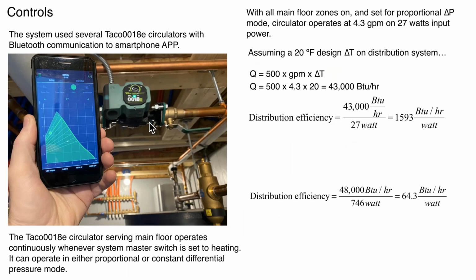There's that little pump that's running that, and there's an example on the phone. It shows you this pump happens to be in right now what's called a proportional differential pressure mode, but it shows you the operating point. It shows you right now it's operating at just under 16 watts at about 3,600 RPMs, and it's only sending out a little under 2 gallons. Now, I want to show you if we were operating this system at full output, that can provide about 43,000 BTUs per hour, and it will do that on 27 watts of pumping power.